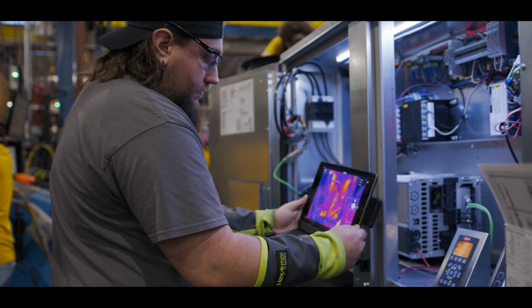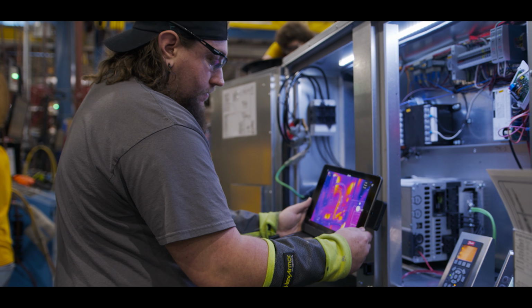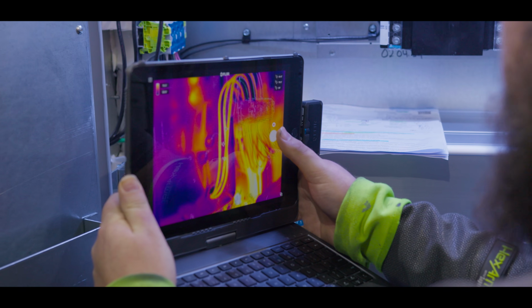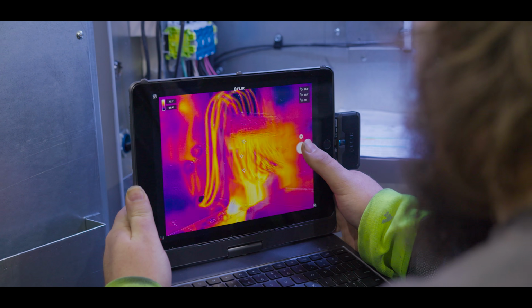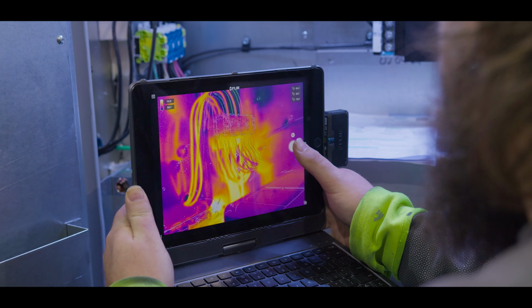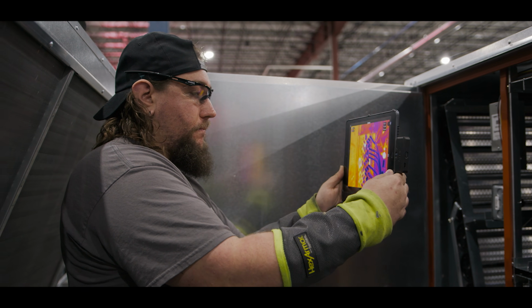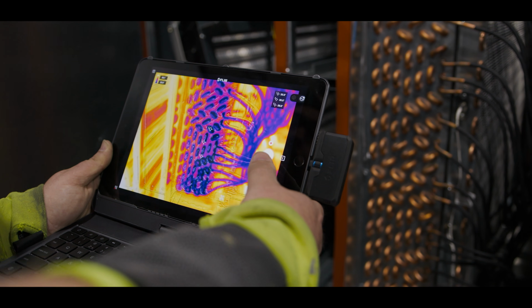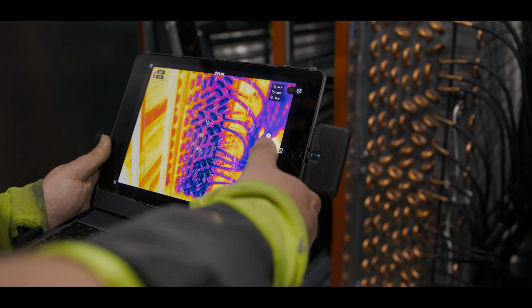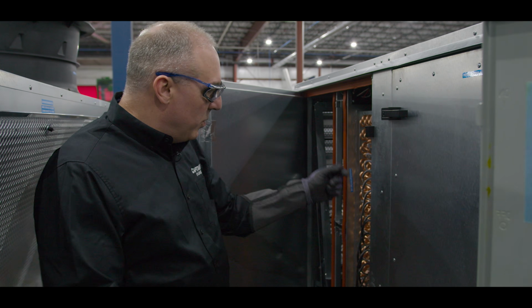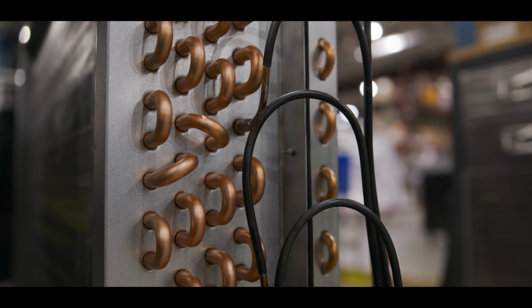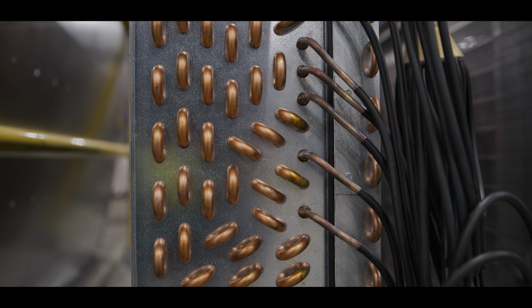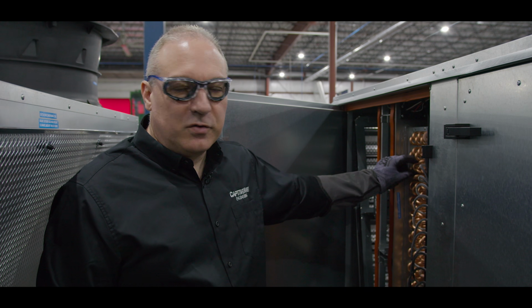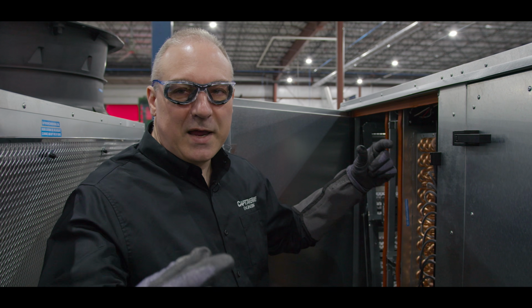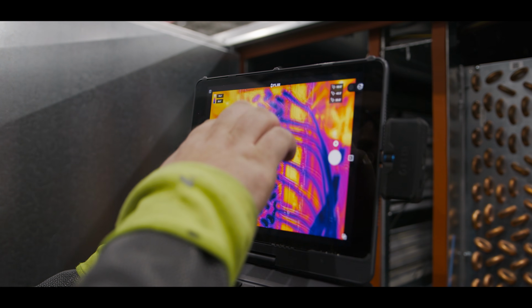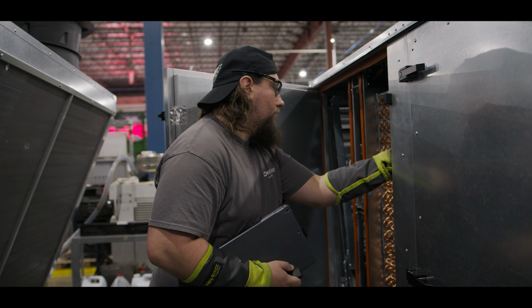If you tighten up a wire and the terminal block is tightened down on insulation, it won't conduct electricity correctly. So using that thermal imaging can help us identify those cases where we'll have a marginal connection or improper connection. We also look at all the coils to figure out if there's any dead circuits in the coils. All of these circuits in the coil will go back through the coil many times. It's possible that a supplier will braze these U-bends, these return bends, on the same ends of the coil, so that will be considered a dead circuit. The thermal imaging will help catch that problem.